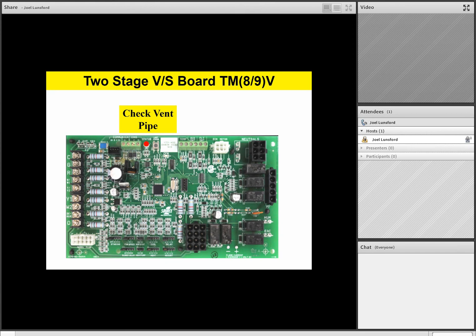Check your vent pressure. Once you eliminate that the vent pipe is okay, double check that vent pressure to make sure the furnace is actually pulling the proper vent pressure to close that switch. Now we're going to talk about how to check vent pressure in some of our next sessions, but make sure you check that vent pressure to make sure that the furnace is actually creating the negative pressure necessary to close that vent switch. What we're trying to say is don't automatically condemn a switch until you check these things first.